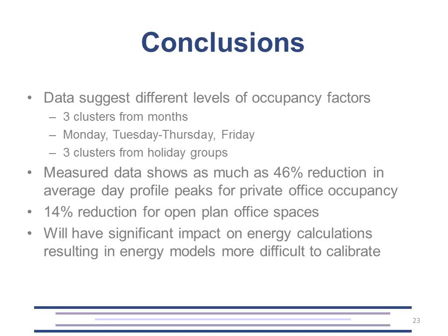So, conclusion: the data suggests that there are different levels of occupancy. Three clusters for months, three clusters for Mondays or the weekdays, and three clusters for the holiday groups. And the measured data shows a 46% reduction in private offices and 14% for the open plan, and they can have a significant impact in the energy calculations, resulting in energy models that can be more difficult to calibrate. So with these diversity factors, I hope that I can eliminate one of those uncertainties in the building model, and you can focus on something else in the energy simulation to calibrate the building.